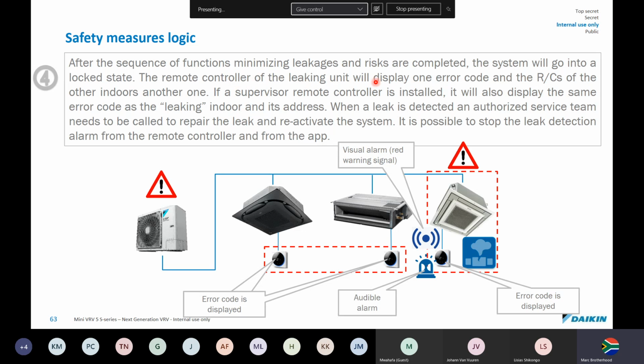The remote controller of the leaking units will display one error code, and the remote controllers of the others another one, which I've mentioned to you already. This is just sort of repeating itself. When a leak is detected, an authorized service team needs to be called to repair the leak, and also identify and see where the leak was, and then they need to reactivate and restart the system. It is possible to stop the leak detection alarm from the remote controller and from the app on the actual unit. Okay, so if you have a cell phone and it's talking only to this unit, you can stop the leak detection alarm and buzzing.